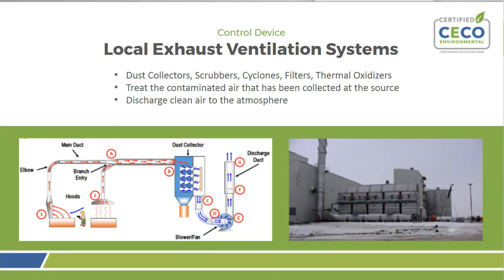Control device. There are many types of control devices, not just dust collectors, meaning filter media inside of a box. You can also have a scrubber. You can have a cyclone or centrifugal collector, and you can have after filters, which may be needed after your initial control device. And then there are thermal oxidizers that destroy VOCs. The idea of that control device is to treat the contaminated air after it's collected, and then you can discharge it to atmosphere or potentially send it back into the plant.